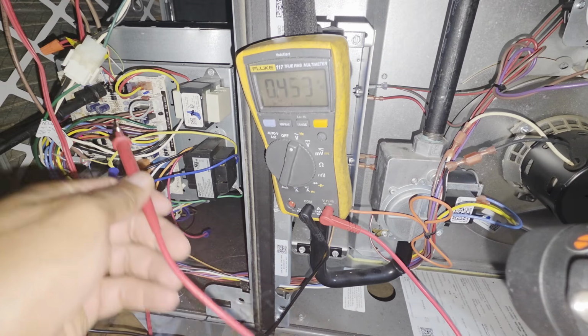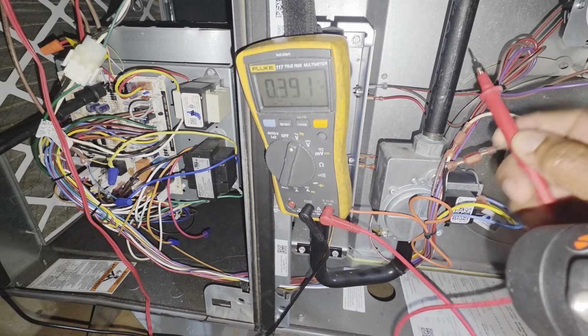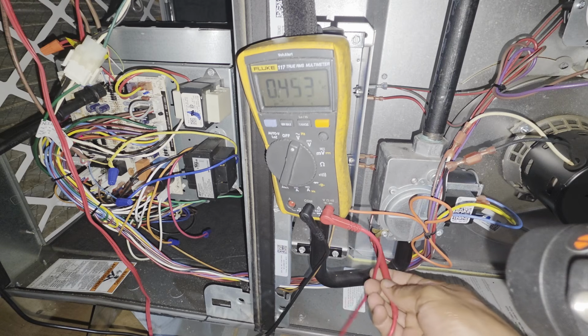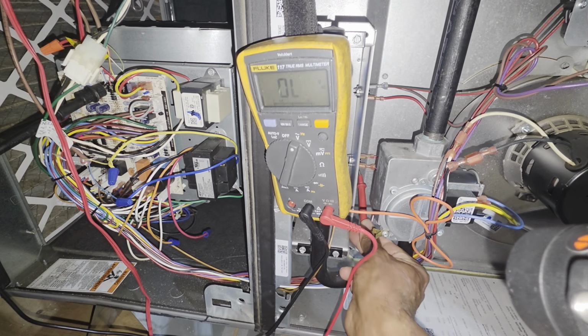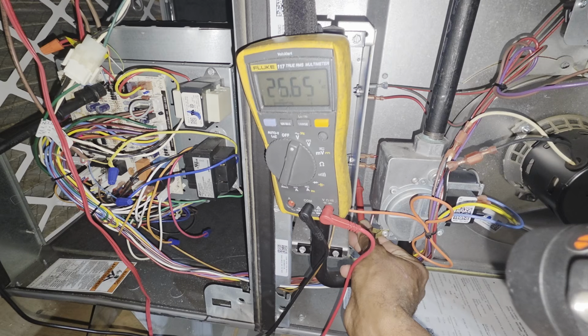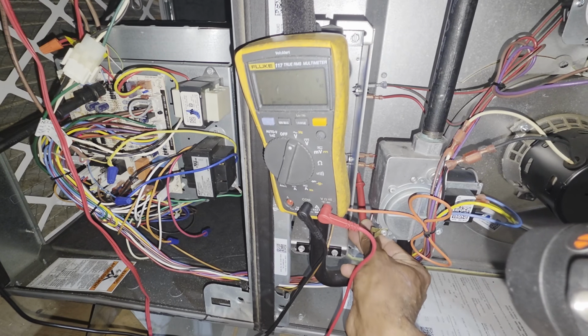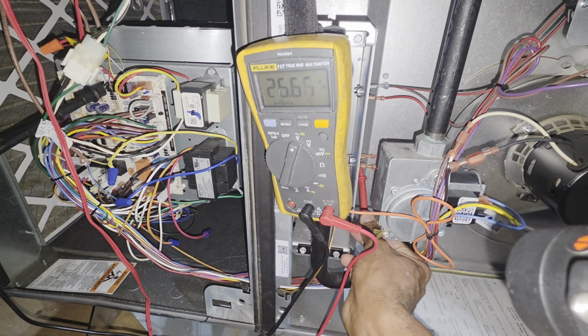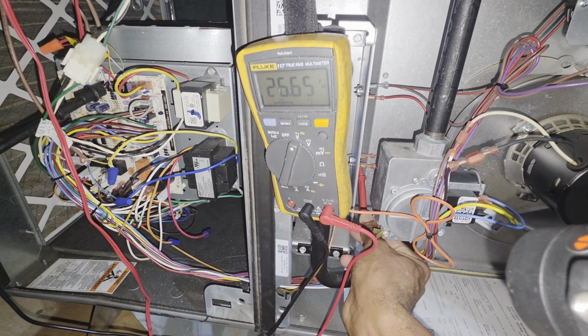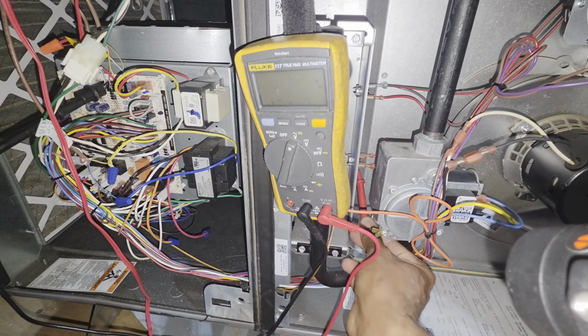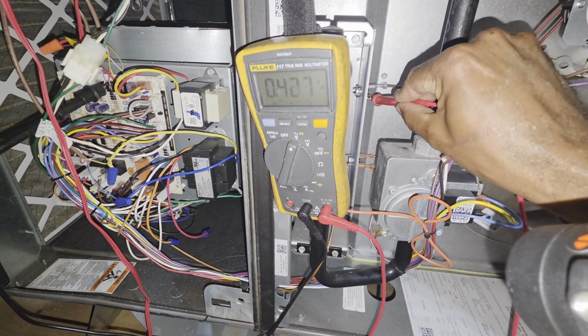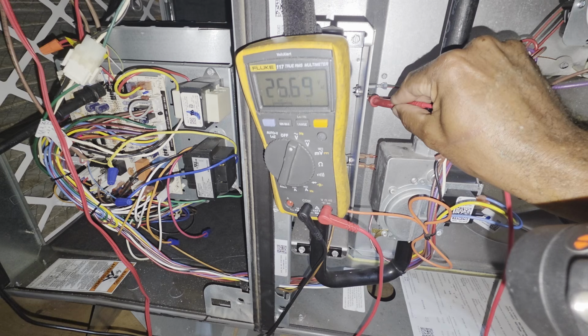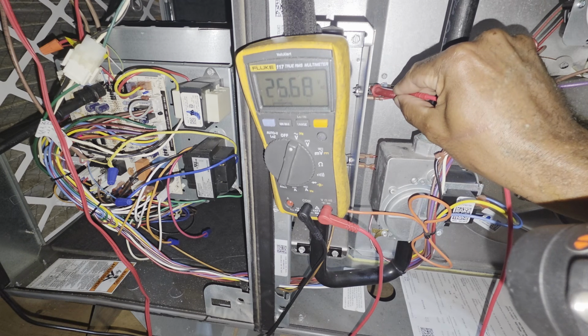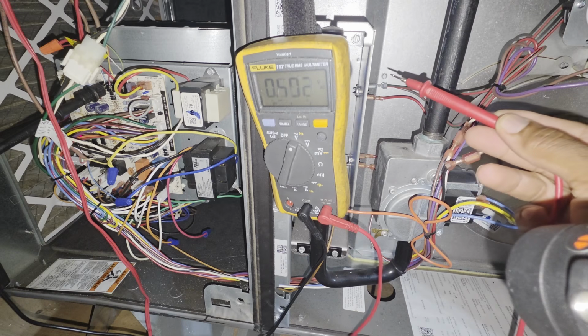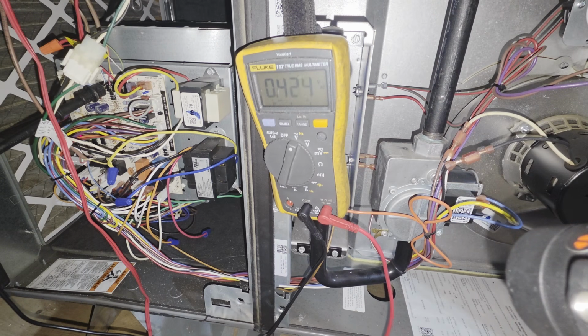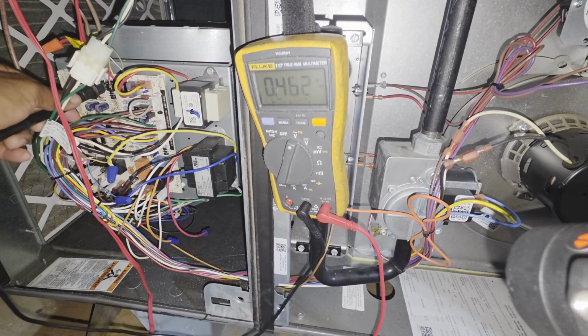All right. So you see, we got us a good pivot. We're gonna go to our 4 terminals right there. One at the bottom. 24 volts. Go to the next one. Pivoting. See that contact? Got our 24 volts. Gonna go to the next. Pivoting. 24, we'll go to the next one. Pivoting. You do want to be careful with these leads and not touch the frame or anything like that. But remember I say, just get us a good pivot.